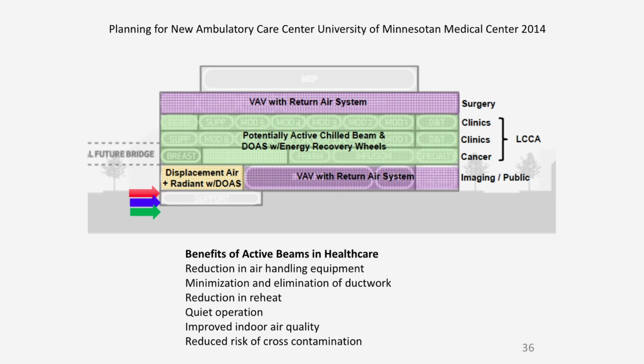The benefits of an active beam include reduction of air handling equipment, because you separate the cooling from the rest of the ventilation needs, like minimum outside air. You cut down on ductwork and reduce the amount of reheat, remember how expensive that was. It's quieter and has improved air quality, though that's something we're waiting to see. We also expect a reduced risk of cross-contamination, which again is something we're learning to see.